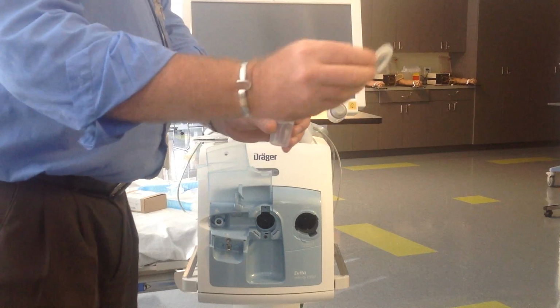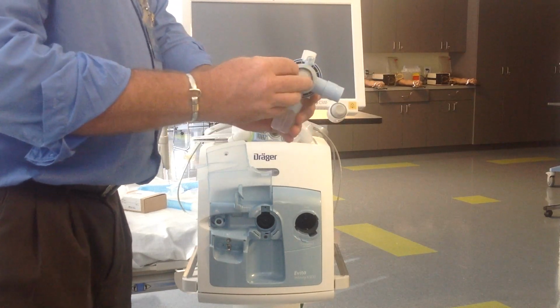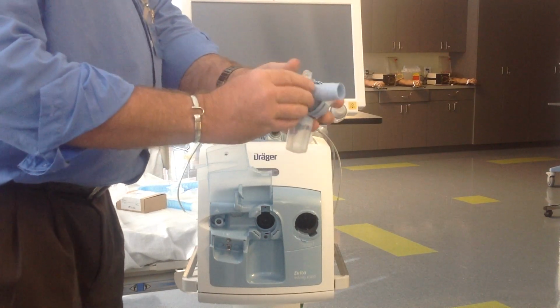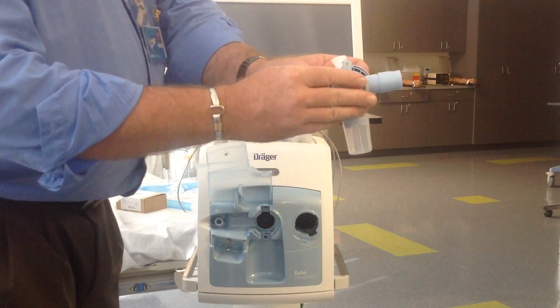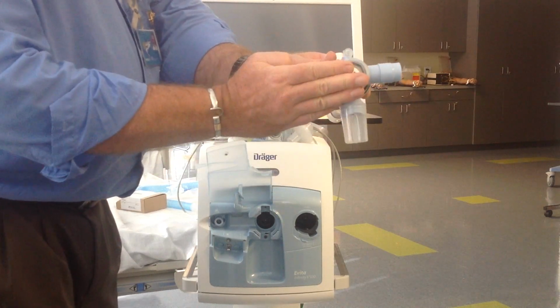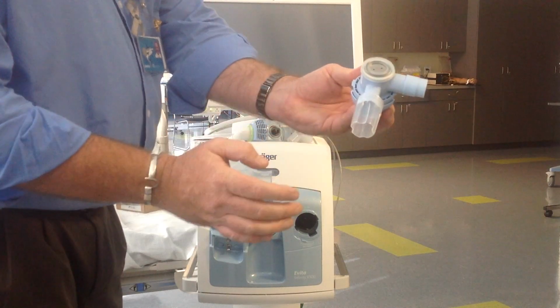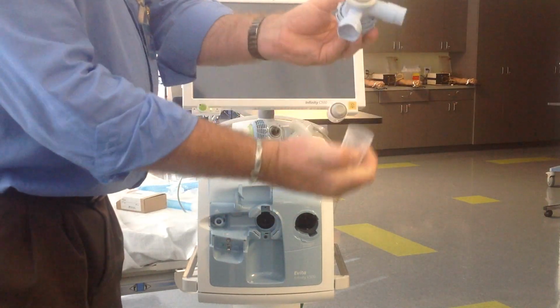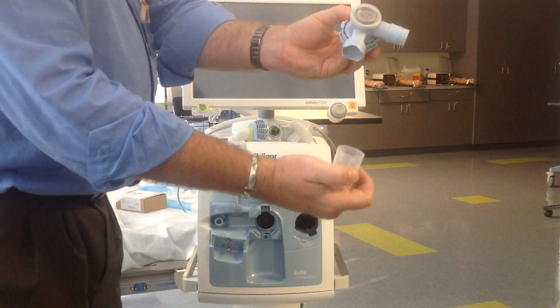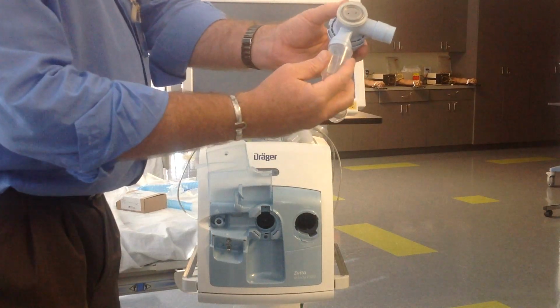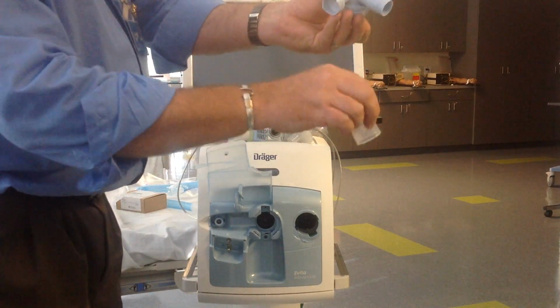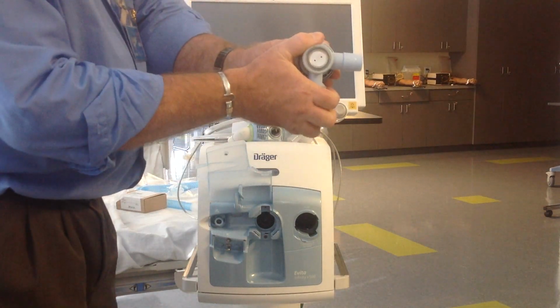You have your diaphragm, expiratory valve. Like many of the other ventilators, it goes just on this section here, and then it sits just like that. This is a water trap in case there's any water dripping off the exhalation valve. It'll catch in this. Once it's full, you just take it and dump it. And that just sits on.